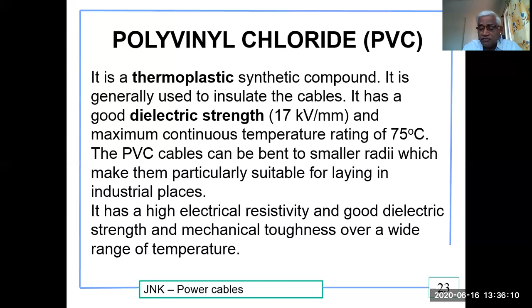Now the PVC cables can be bent to smaller radii, which makes them particularly suitable for laying in industrial places. It has a high electrical resistivity, good dielectric strength, mechanical toughness over a wide range of temperatures. Same thing, it is non-hygroscopic. Hygroscopic means it absorbs the moisture. Non-hygroscopic means it does not absorb the moisture.